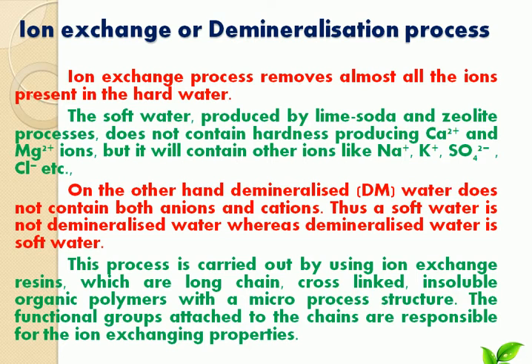Both cations and anions are removed from water by the ion exchange process. The soft water produced by lime-soda and zeolite processes does not contain hardness-producing calcium and magnesium ions, but it will contain other ions like sodium, potassium, sulfate, and chlorine. Demineralized water does not contain both anions and cations. Thus, soft water is not demineralized water, whereas demineralized water is soft water.